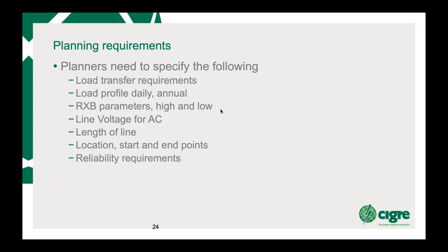You also need to understand what happens with the voltage at the receiving end. Do you need to have compensation if you have an SIL that is too high? You also need to understand the voltage, of course. Is it 400 or 275? We need to know the length, start and end points, and then what reliability requirements there are.